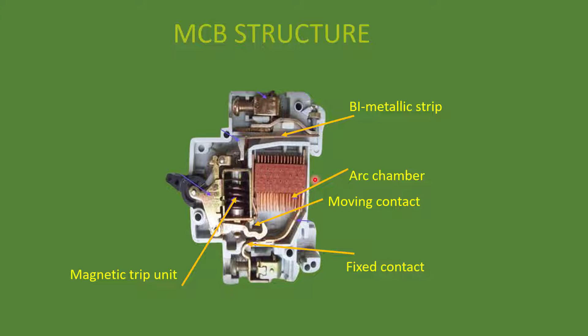The other part is the arc chamber. The arc chamber is the arc extinguishing mechanism. Due to the sudden disconnection of contacts, an arc is produced because of the ionization of air, and we have to extinguish this arc. The arc chamber divides the arc into small portions — you can see different small chambers inside the arc chamber. As the arc passes through these chambers it is divided into small portions, loses its power and force, and is extinguished.